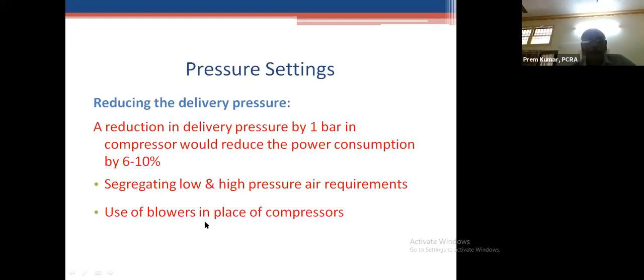Pressure setting is very important. It is standard for many companies to follow the standard pressure, but it is always important to revisit machine to machine and adopt only the required pressure. Where multiple pressures are required, it is better to go in for low and high pressure systems. In areas like STP, sewage treatment plant, where the pressure is low, 1 to 1.5, use low pressure blowers in place of compressors.